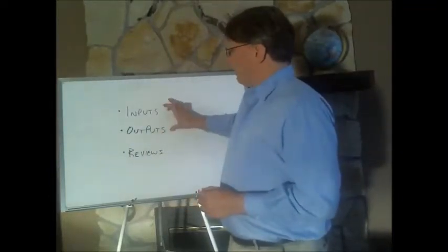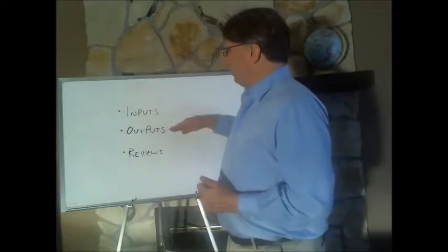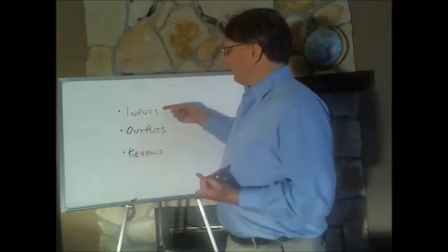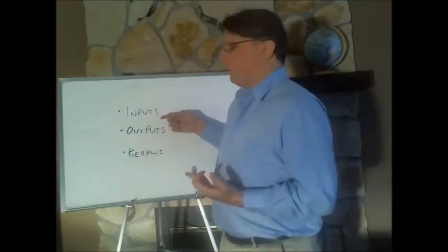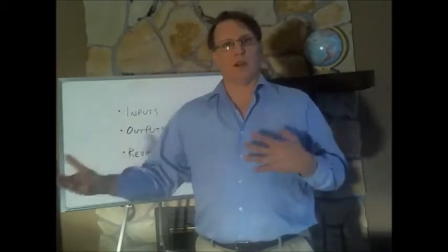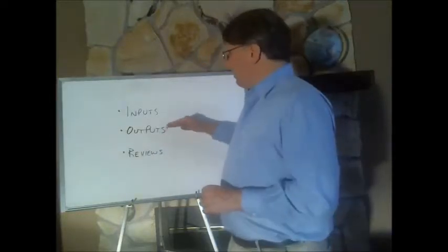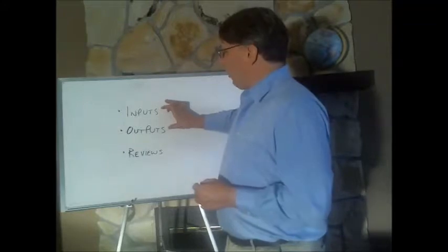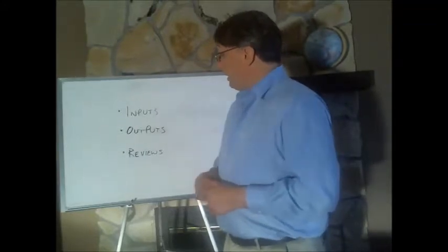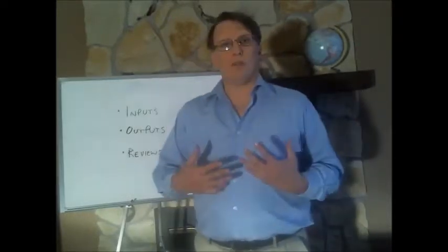There's obviously a step in here that's not just confirming the outputs, but I call the homework of getting to that point. Understanding what's risky, doing the limit testing of your process, of your product, to know where it performs, where it likes to be, where it struggles to be, and then proving that, and that's part of that design output. So there's a lot of homework that goes in between those steps. The intermediate steps as well as the final steps are reviewed in the design reviews.